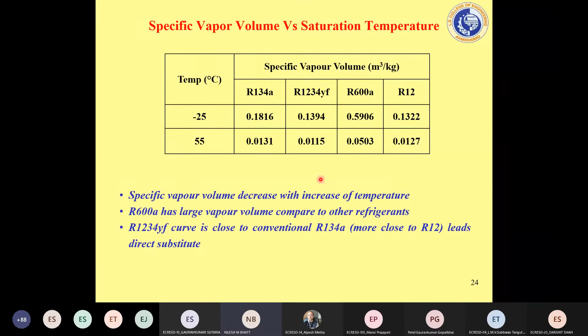Now these numbers are calculated for a condenser temperature of 55 degrees centigrade, pressure drop in the evaporator 0.5, pressure drop in the suction valve 0.1, and pressure drop in the discharge valve 0.25. These numbers are not randomly taken. They are taken based on the 10-point cycle analysis as per the Bureau of Indian Standards, which we will discuss in a short while.